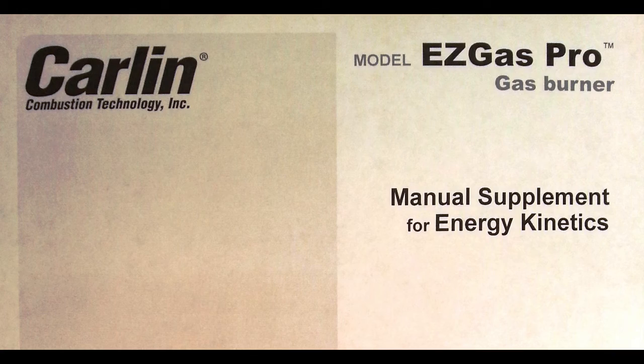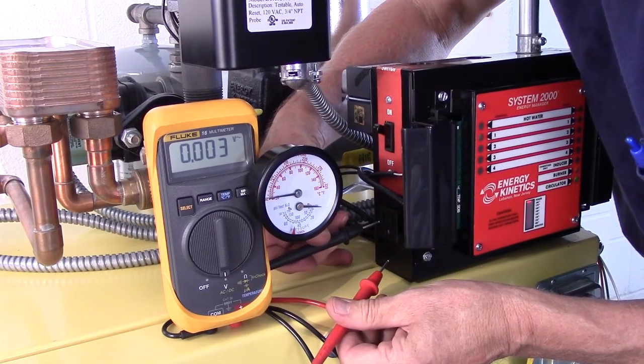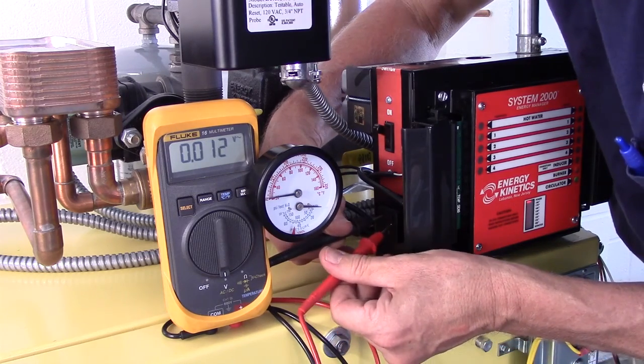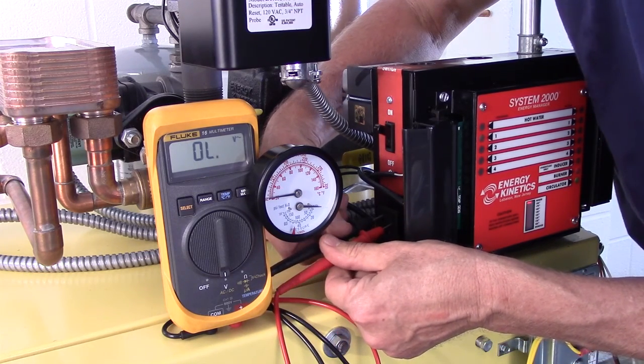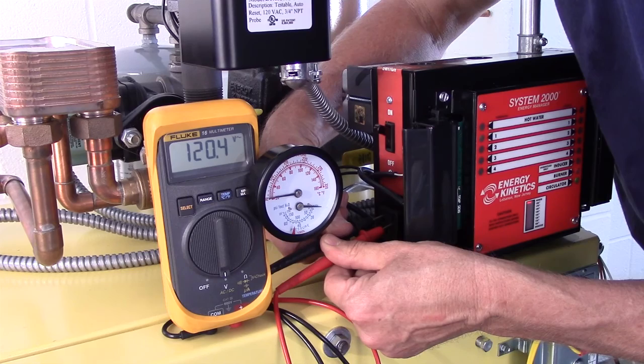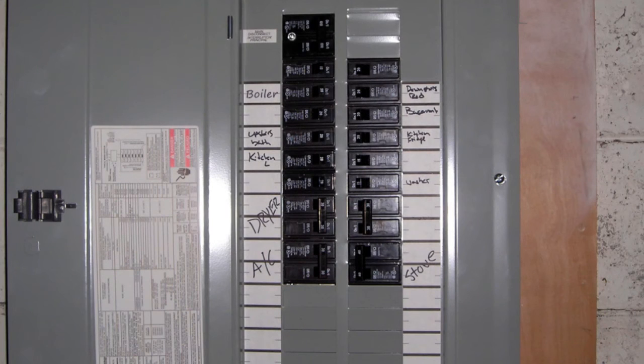Adjust if necessary. You must also check the polarity of the power supply. If the hot and neutral wires are reversed, the flame rod circuit cannot sense the flame correctly and the primary control will lock out after the trial for ignition period. A continuous copper ground must be in place from the power supply panel to the burner junction box for reliable sensing of flame by the primary control.